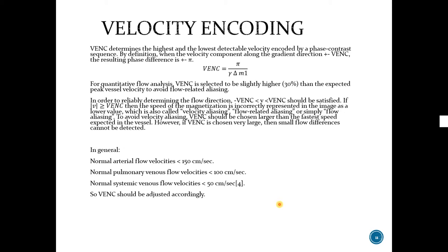Velocity encoding, or VENC, is an important parameter in PC MRI. It basically determines the highest and lowest detectable velocity. This is how it is expressed. For quantitative flow analysis, VENC is selected to be slightly higher than the expected peak vessel velocity to avoid flow-related aliasing. So what happens if we choose VENC less than the peak vessel velocity? Then we will have a velocity aliasing problem, where the speed of the magnetization is incorrectly represented. To avoid velocity aliasing, VENC should be chosen larger than the fastest speed expected in the vessel. And if we choose very large, then we will have another problem. In that case, small flow differences cannot be detected.